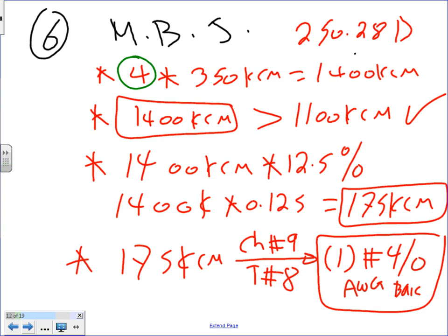The number of sets? No, how did you get that number 4 hot? Because you need to find 175 kcm. So go under the kcm column and find 175 or larger, and cross-reference it with the number.